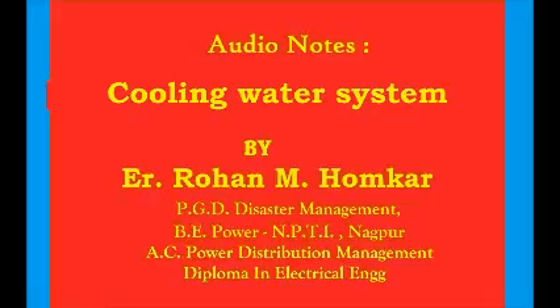The hot water coming out of the condenser cannot be used again in a closed system without pre-cooling. It is because the hot water, if used again, will not be able to absorb the heat as TW2 reaches near Ts. The saturation temperature of the steam at condenser pressure and the condenser vacuum cannot be maintained. Therefore, it is absolutely necessary to pre-cool the water coming out of the condenser before using it again.